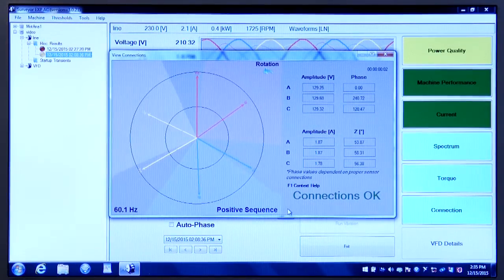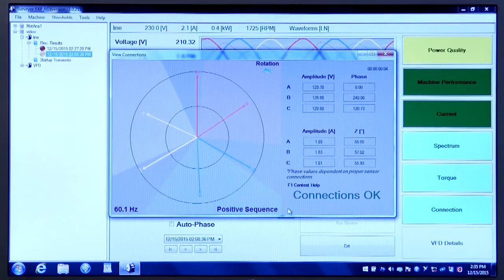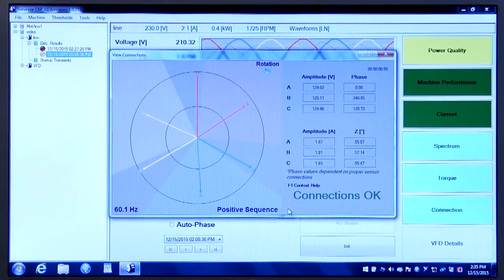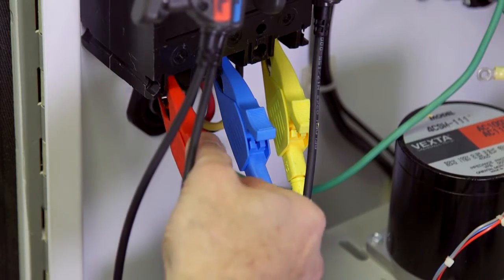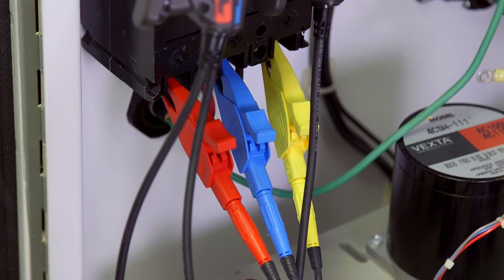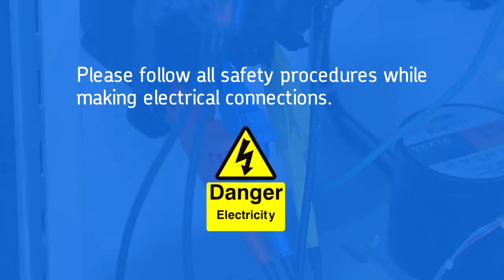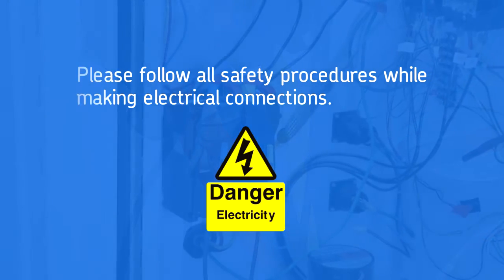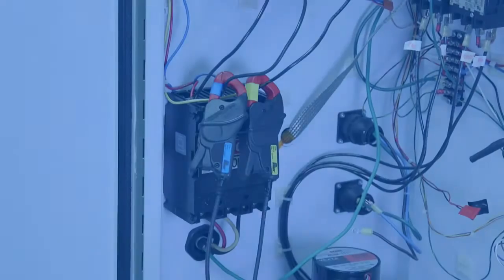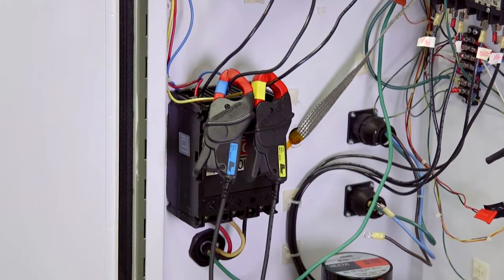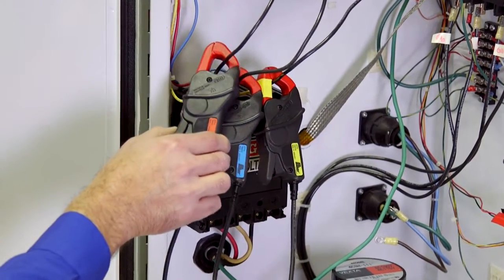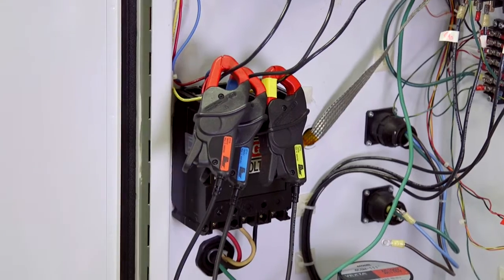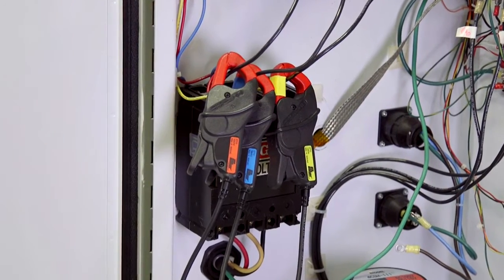The EXP 4000 is connected to the voltages and currents running the motor. Voltages less than 1000 volts can be connected directly, paying attention to all electrical safety practices. Often the EXP 4000 is connected to metering PTs and CTs, which reduce the voltage and current to low levels.